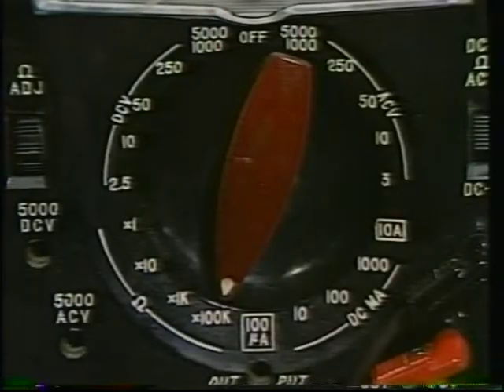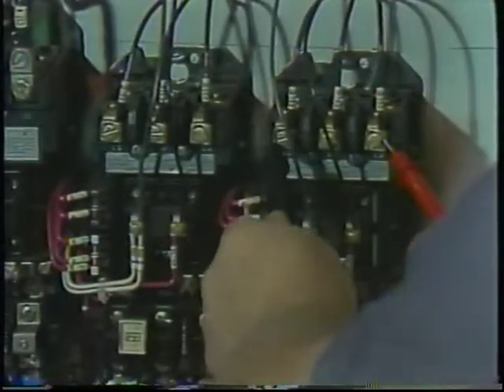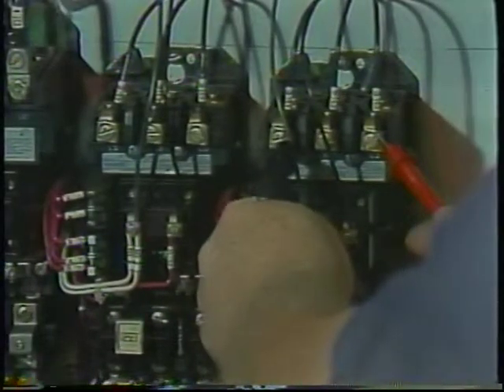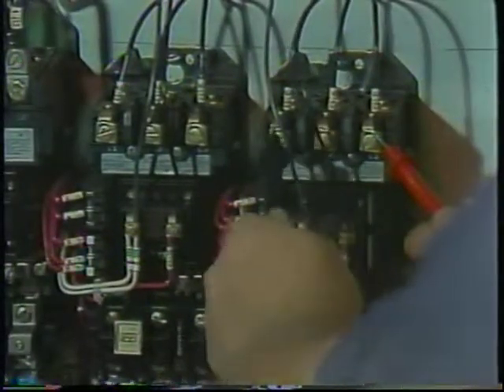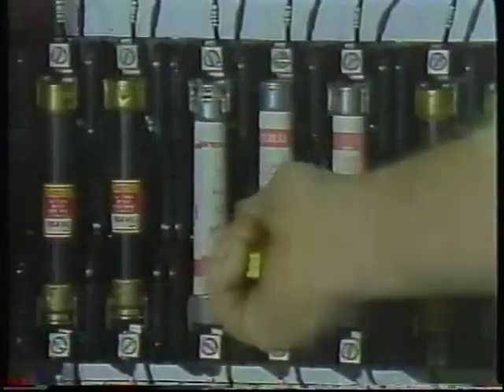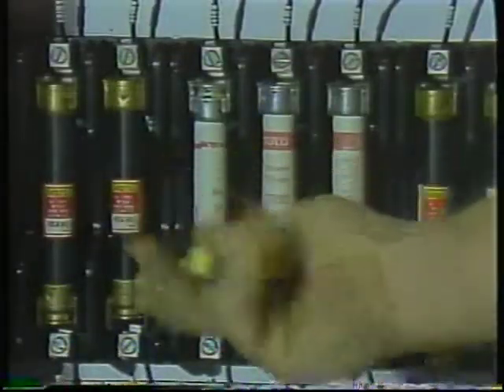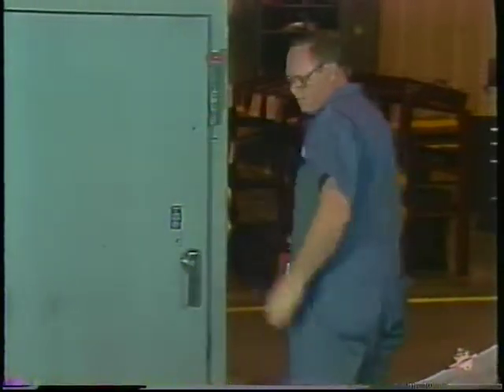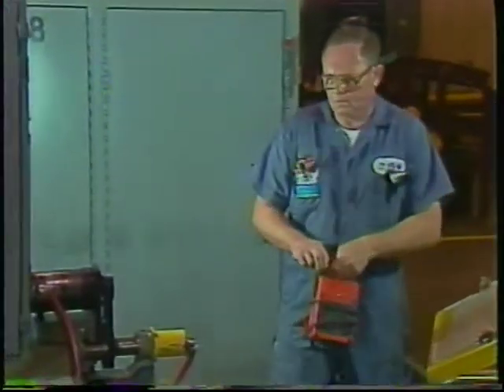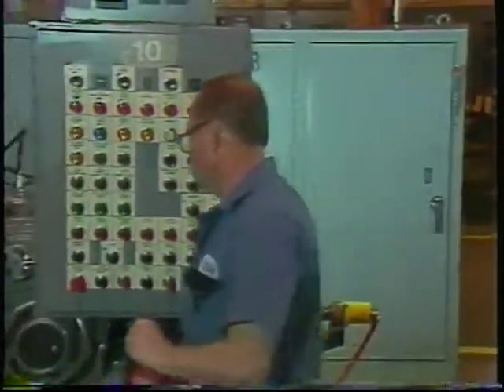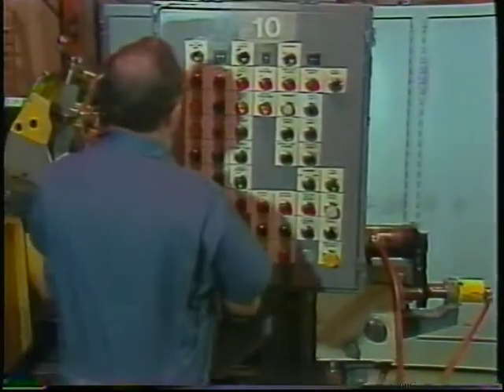Then, take a resistance reading on the lines out of the main box. If the resistance is high or infinite, and it will be in the case we are supposing, you can replace the fuse or reset the breaker. Be careful here. Even though you are pretty sure you are not switching power onto a shorted line, stand to one side and look away. If the fuse or breaker holds, you can eliminate the lines to the starter and the input side of the starter itself.